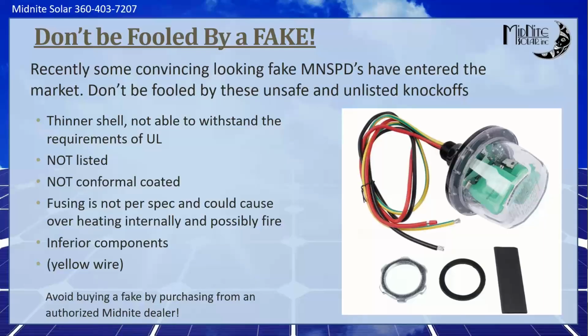So why should you steer clear of this one? Many reasons. So one is the plastics are much thinner and probably not the right material. I haven't actually tried to light one on fire yet, but they are definitely much thinner, about half the thickness of the one that we use. And that's important because under certain conditions, either a direct lightning strike, those MOVs inside explode, and the plastic contains that. Sometimes we see the plastic crack, but that is what that's there for. Those SPDs will explode under a direct strike, and that contains it.